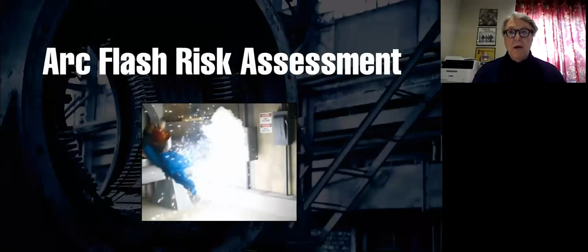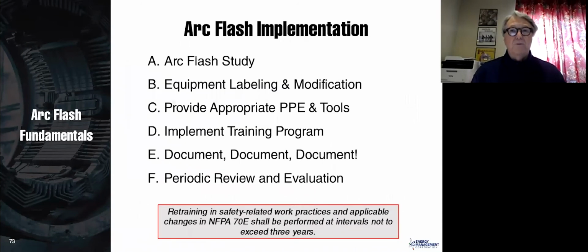and it makes it much safer for those who are using high resistance grounding. And finally, we get into our arc flash risk assessment. We do the arc flash study, then the equipment labeling and modification, provide appropriate PPE and tools, implement a training program, document, and then you have to review your arc flash every 5 years. That review simply amounts to, has anything changed? And if it has, then you need to update in order to add those changes. If nothing has changed, you're done. You've already done your evaluation.